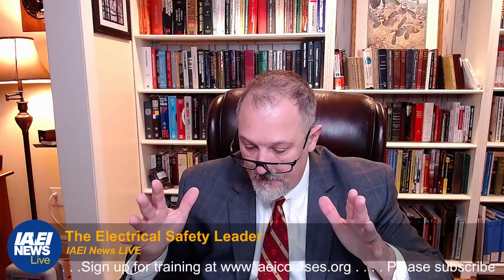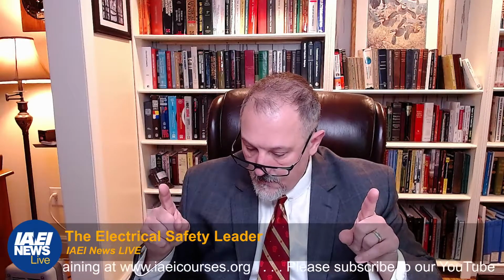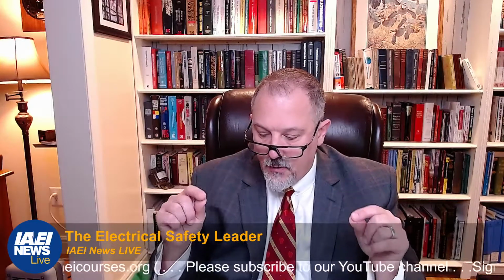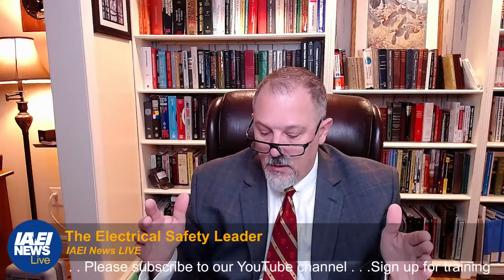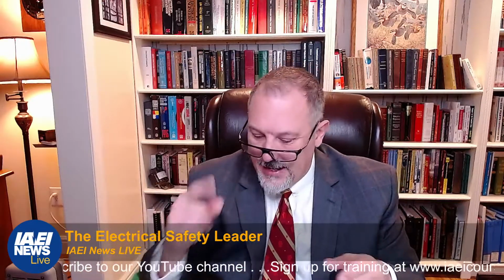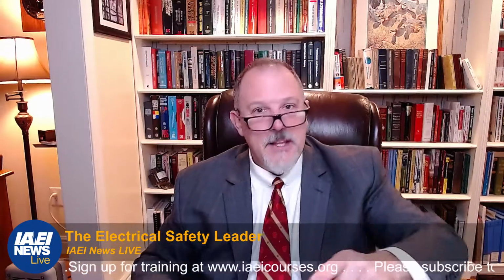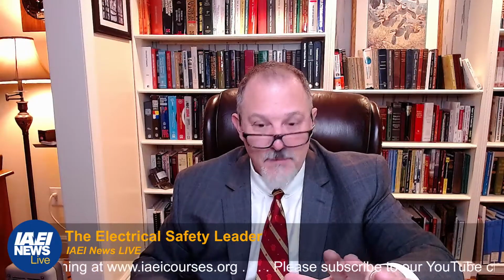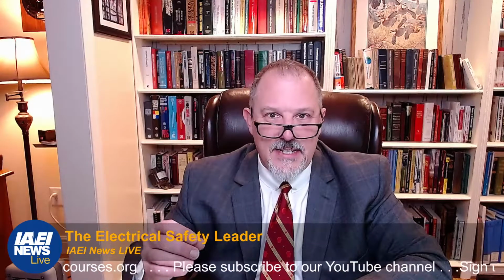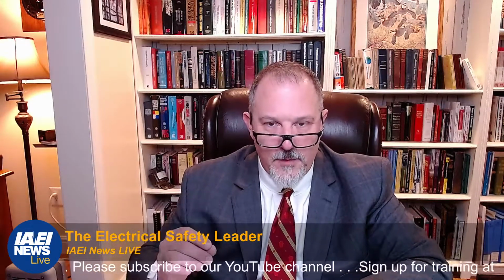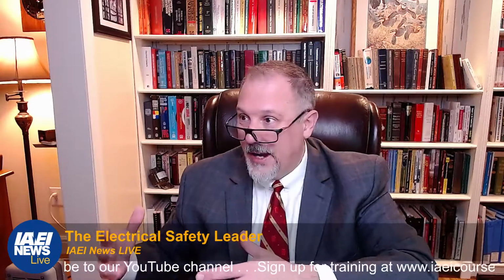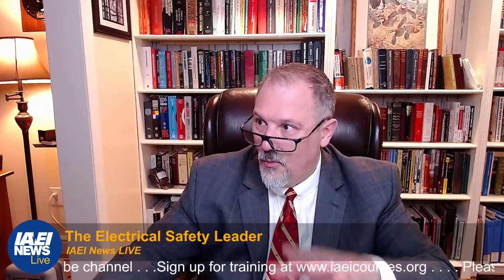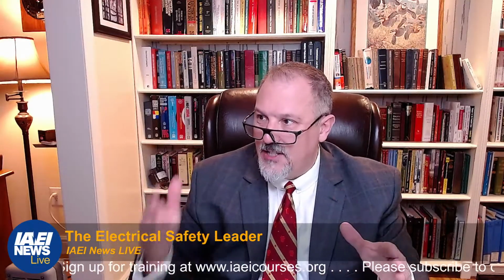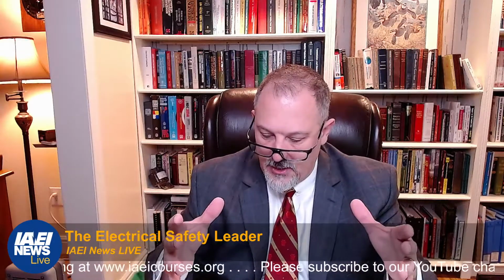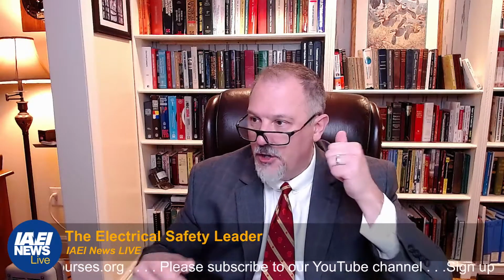So what they did, I'm liking this. They took 110.3 and 110.4. They eliminated energized work, the 110.4. And Robert, I know you and I talked about it, and I had it marked in my book. I had justified energized work. And we talked about this in different forums, that it says energized work, but we have to emphasize it is only justified energized work that can be performed. It's not just energized work. And those are in other areas. So they reconstructed 110.2 titled Electrically Safe Work Condition. Put the emphasis on that, focusing on your policies.